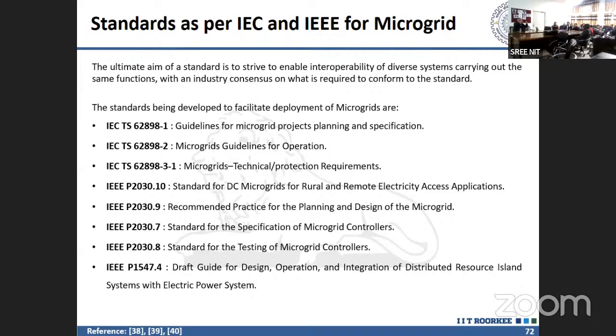So what you are doing, I have the voltage transmission line, and here I am basically feeding the power. So when the load is reducing, here the overall voltage is increasing. Now you are feeding more power from the solar side, so this will give a boost to the voltage. Same as you will have in the Ferranti effect, your load is being reduced and voltage is increasing, so that voltage will increase at your terminal point.